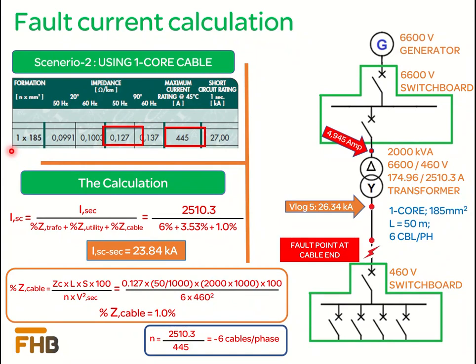We are discussing this second scenario to notice the effect of taking single core cable instead of four core cable of the same size 185 mm² on the short circuit current. First thing to notice is that the current carrying capacity of the single core cable is more than the four core cable. Therefore the number of cables per phase are reduced to six cables.